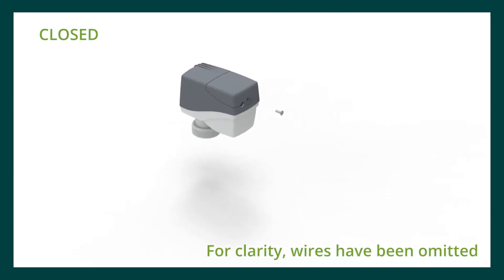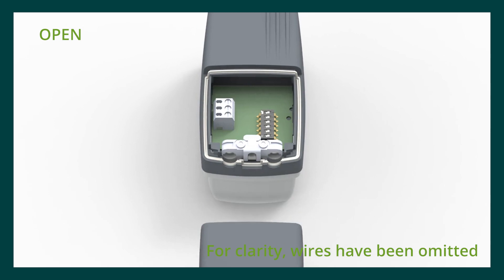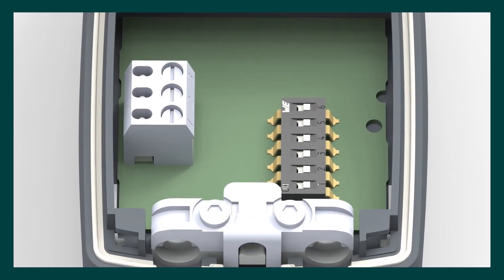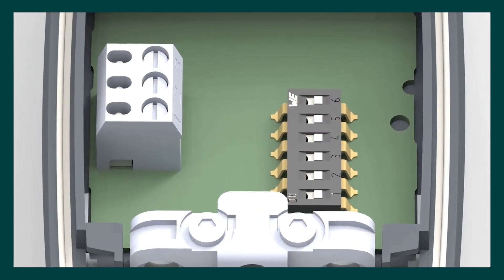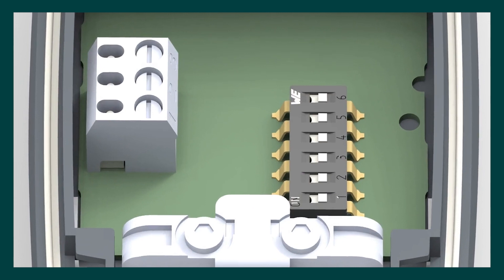To set up the FN04 actuator dip switches, unscrew the set screw and lift off the cover. The default setting for all the dip switches is the off position which will satisfy the majority of applications for the green PICV. Switching the dip switch to the on position changes the function.